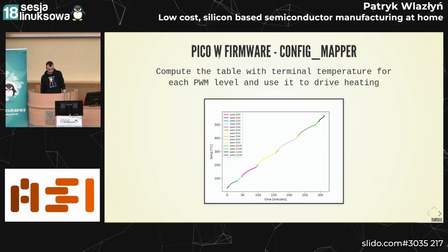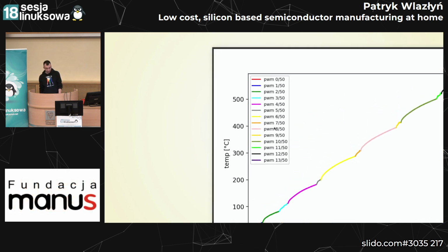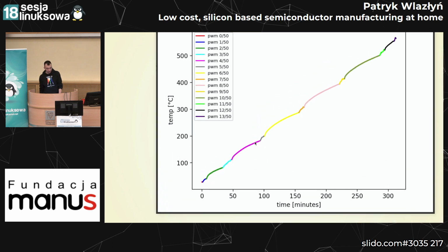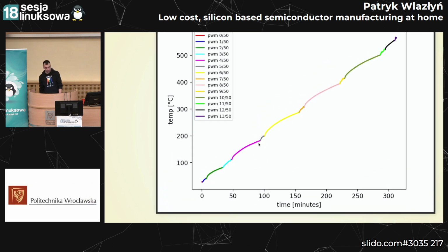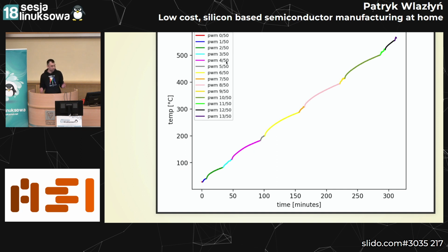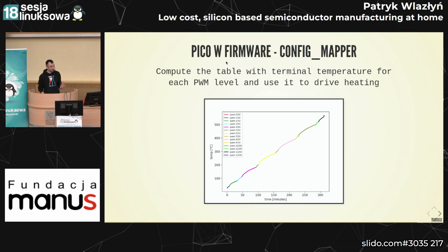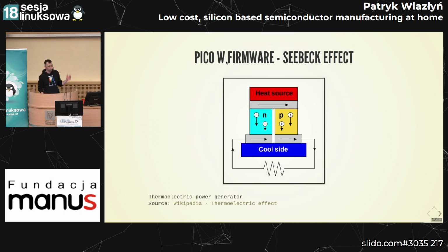We also have a way to pre-compute a table for each PWM level, showing what terminal temperature the furnace can reach and be driven to at that level. For example, at PWM level 4, the terminal temperature we can reach is around 200 degrees C. So if we want to reach 200 degrees C, it's probably good to just set PWM to 4 and wait. This is another way of steering the furnace, and it works better than PID.